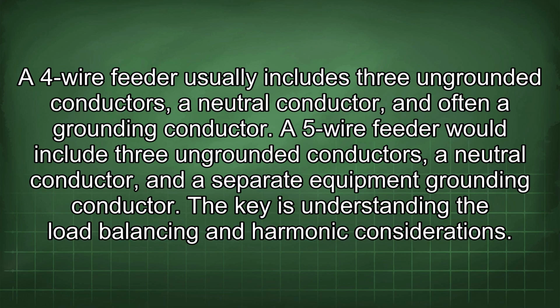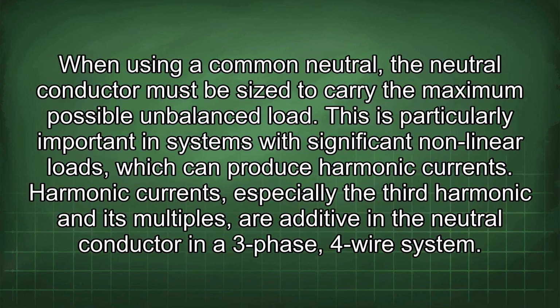The key is understanding the load balancing and harmonic considerations. When using a common neutral, the neutral conductor must be sized to carry the maximum possible unbalanced load. This is particularly important in systems with significant nonlinear loads, which can produce harmonic currents. Harmonic currents, especially the third harmonic and its multiples, are additive in the neutral conductor in a 3-phase 4-wire system.